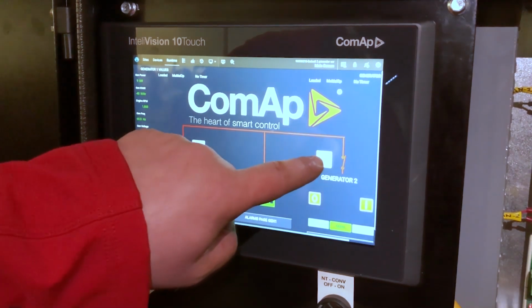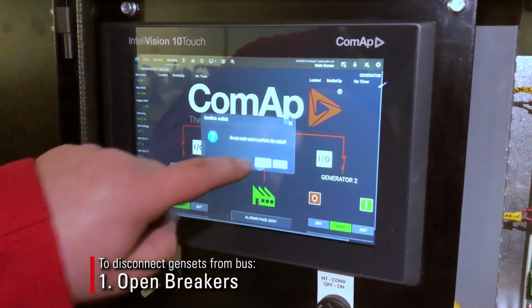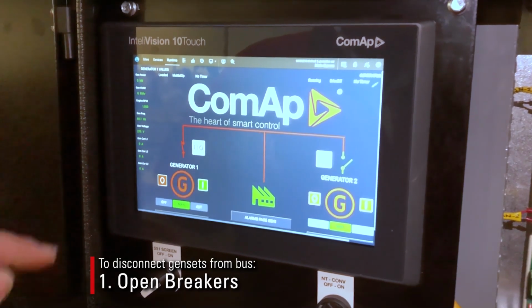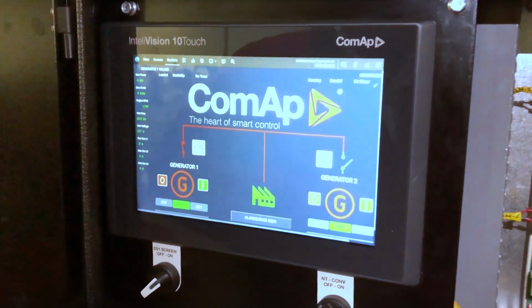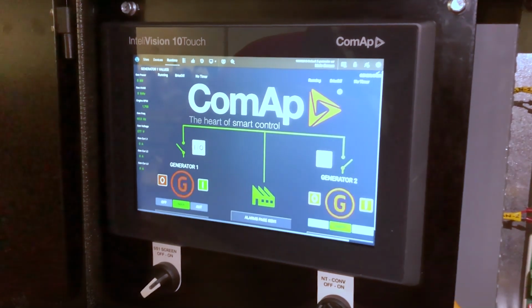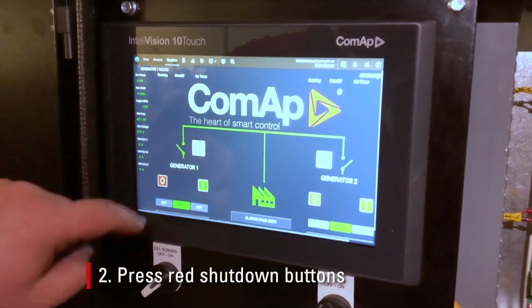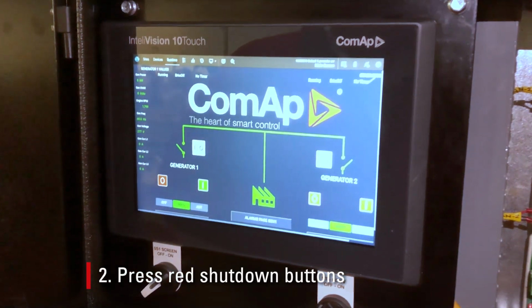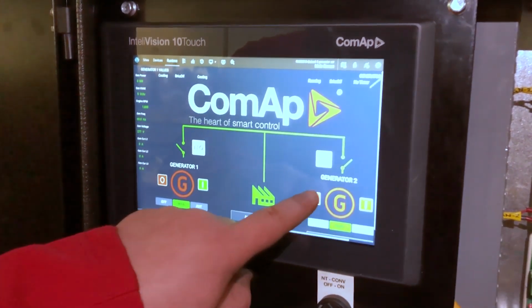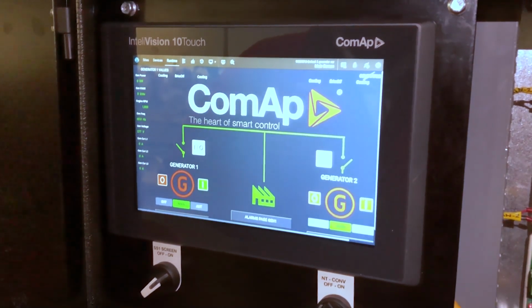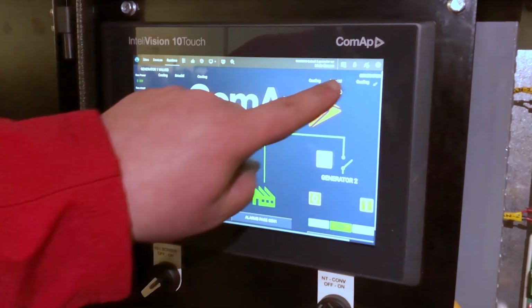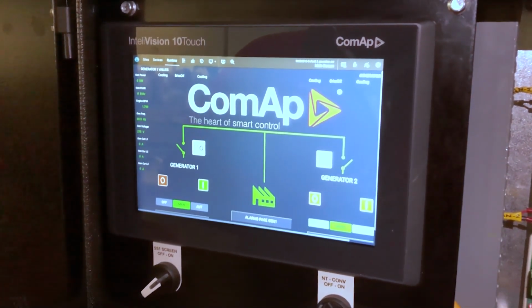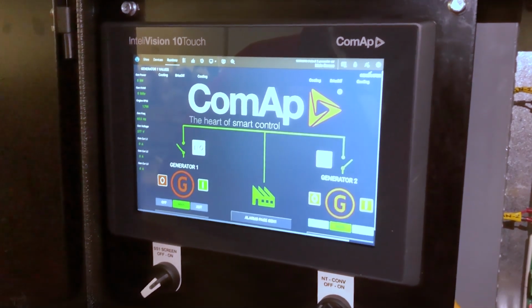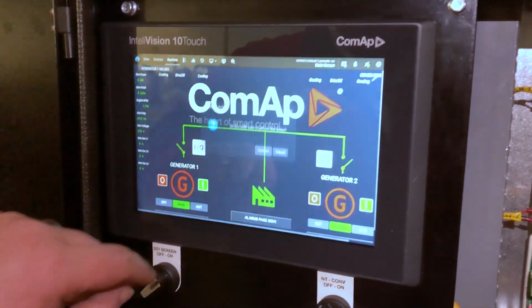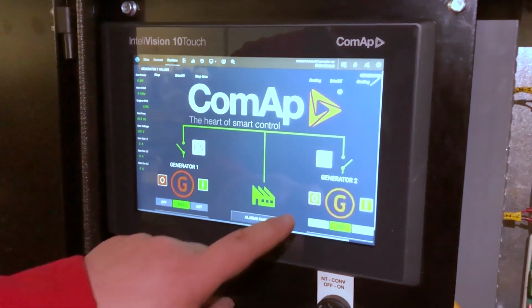Now if you want to disconnect the gensets from the bus, you will need to open the breakers. Now both generators are removed from the bus. Next, if you want to shut down the gensets, you will press the red shutdown button. Once the shutdown buttons have been pressed once, the gensets will begin their cooldown sequence. Please note the standard cooldown timer is set to 30 seconds, but this may vary. When the cooldown sequence has begun, it will be indicated at the top of the screen. If you needed to stop the generators immediately, you can press the shutdown button a second time.